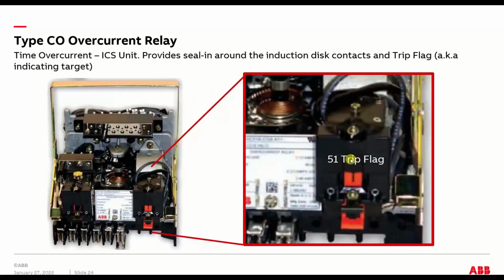This is the last piece. It's just an extra contact, but I noted it because it also contains a trip flag. So the relay actually has two trip flags, one for the time overcurrent element, which is here, and one for the instantaneous. So in this picture, you can see that this relay had tripped on time overcurrent.